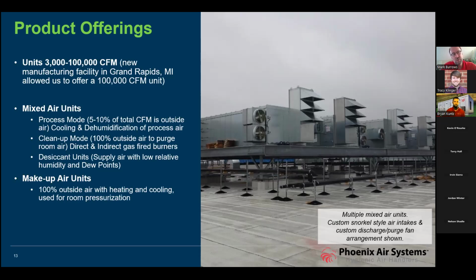Some of the slides we showed before where you have ceiling hung units which are doing fine and you have an issue with positive pressure, we can certainly provide a small makeup air unit, which is all outside air with cooling and heating, putting in a certain temperature or a predictable temperature all the time.